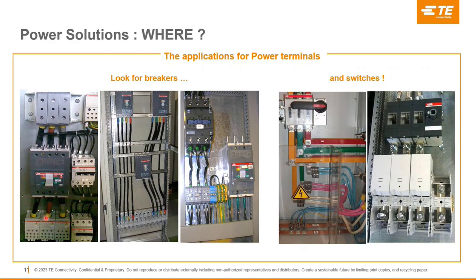In the second image, you can see the output tabs of each MCCB have been grounded and terminated at the bottom of the panel, where stud type terminal blocks can be employed. In the third application, the outgoing of the breaker is shown, where each individual outgoing has been connected to a dual terminal block, and those terminal blocks have been shorted with a shorting link. That's one way to do it.